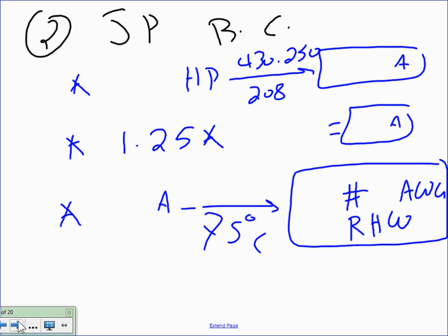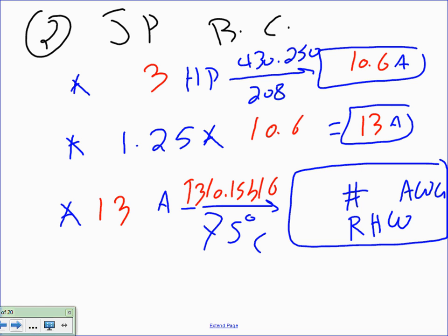All right, so let's go to the jockey pump. For the jockey pump, I have 3 horsepower, guys. Same table, same voltage, so I get 10.6 amps. You multiply by 1.25 because it's a continuous load, which gives you 13 amps. Out of the 13 amps, you take it to table 310.15(B)(16). Anybody know why we go to the 75 column, not 60, even though we're less than 100 amps? They're motors. When you deal with 3-phase equipment, 99.9% of the time the lugs are rated for 75 and we size based on 75. If you're dealing with single-phase equipment, then the 100-or-less rule becomes a big rule. If the equipment is 100 amps or less, 60; more than 100, 75; except for motors, even single-phase motors.